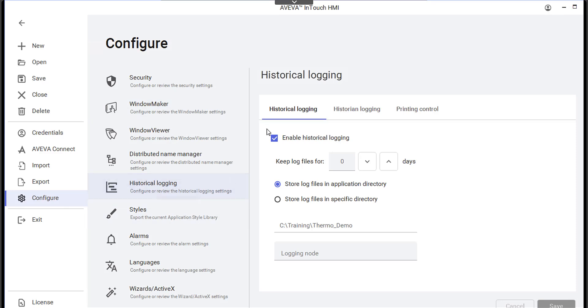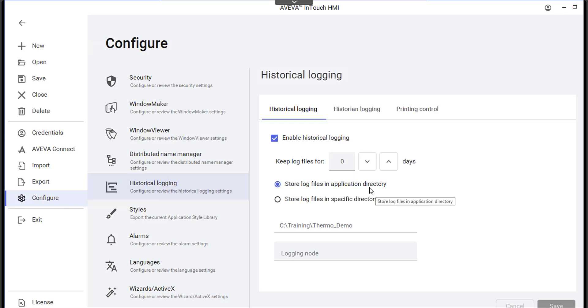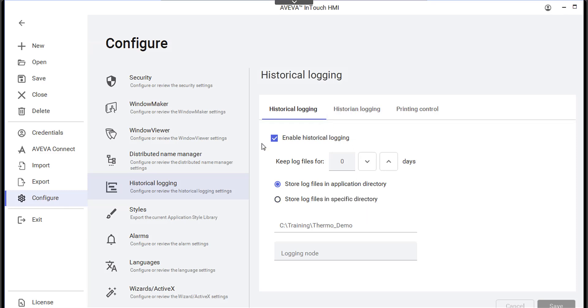If you click on Historical Logging, the first step is enabling historical logging within the InTouch HMI application itself. You get to store those LGH files in either the application directory, which is the default location, or you can choose to store them somewhere else. I've made sure to enable that since this is what we're discussing today.